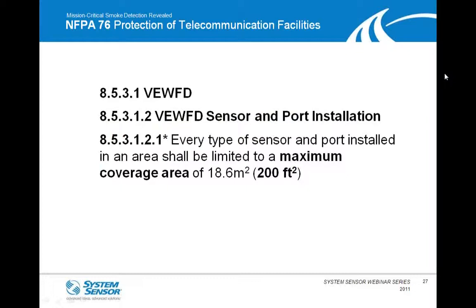Okay, specifically for very early warning, it basically says that every type of sensor or port installed into the area must be limited to a maximum coverage of 200 square feet. So if we look at standard detection, as laid out with NFPA 72, that standard sampling point or sampling port is good for 900 square feet of coverage. To meet very early warning, that's ratcheted all the way down to 200 square feet.